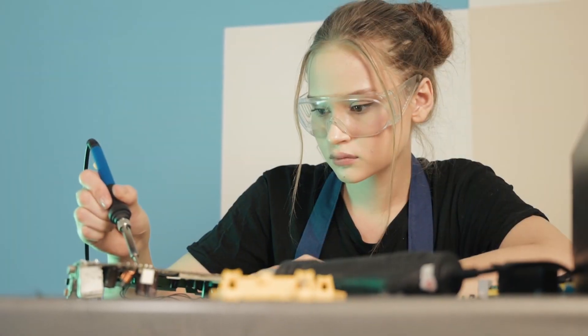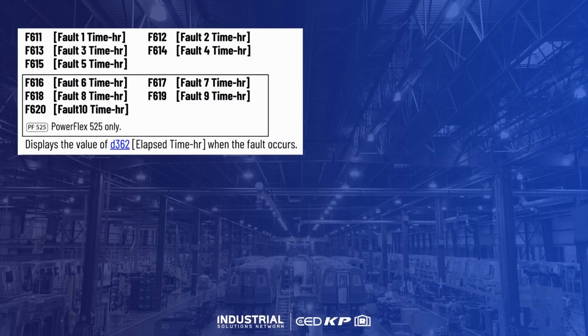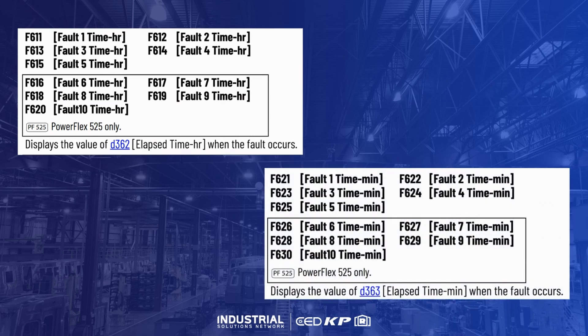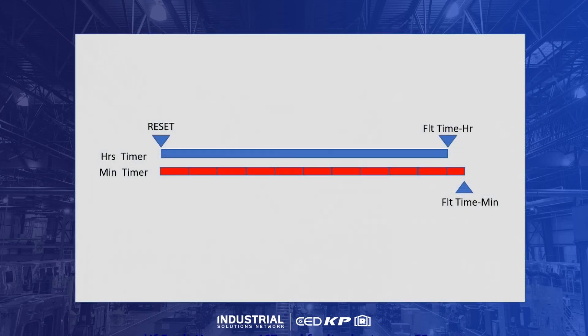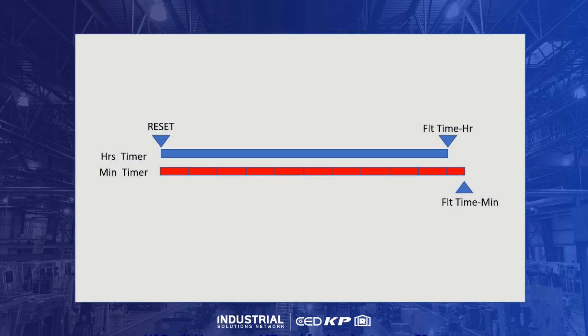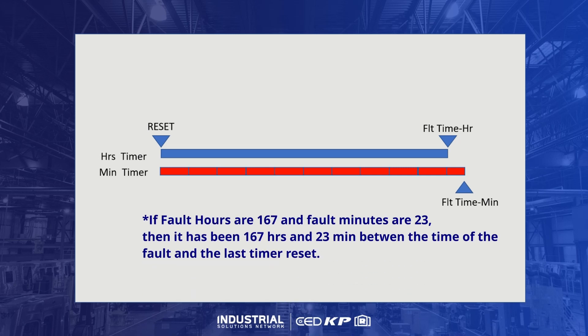Let's take a closer look at the associated fault code parameter data. Starting with the timestamp data, we see that it's divided between hours parameters and minutes parameters. Each parameter will provide the hour and minute timestamp for the associated fault. The fault hour timestamp provides the number of hours between the drive's timer last being reset and the time of the fault. The minute stamp provides the number of minutes from the hour. By noting the hour and minute timestamps between faults, a picture of event frequency may be built.